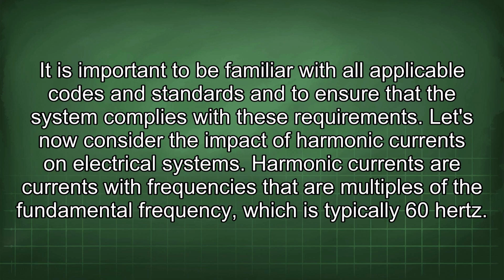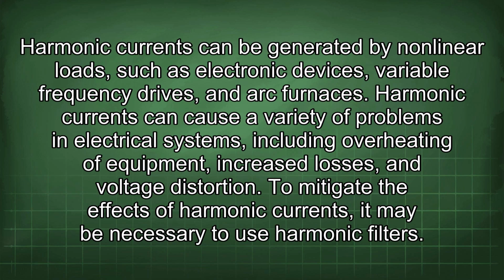Harmonic currents are currents with frequencies that are multiples of the fundamental frequency, which is typically 60 Hz. Harmonic currents can be generated by nonlinear loads, such as electronic devices, variable frequency drives, and arc furnaces. Harmonic currents can cause a variety of problems in electrical systems, including overheating of equipment, increased losses, and voltage distortion.